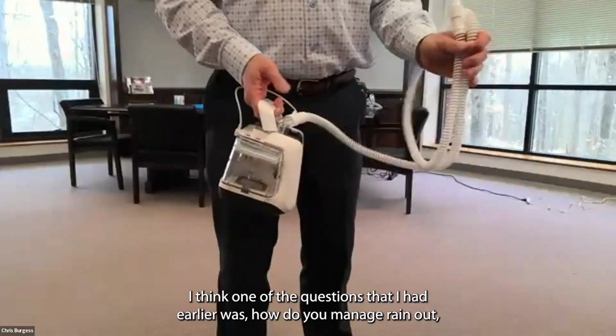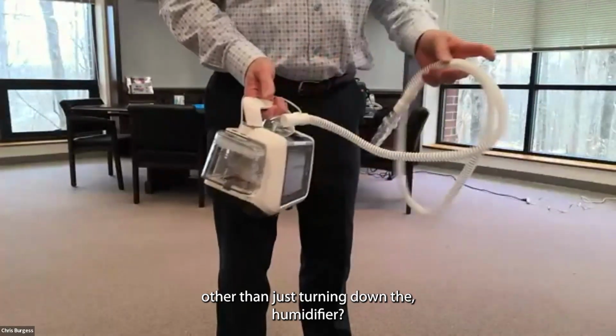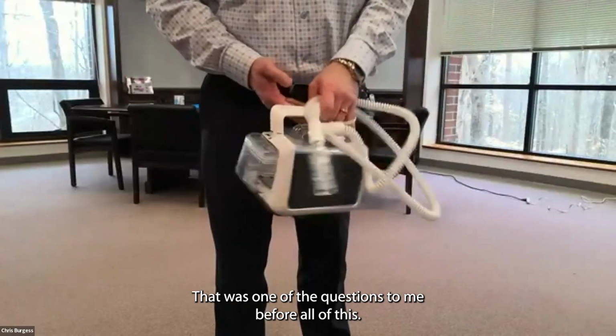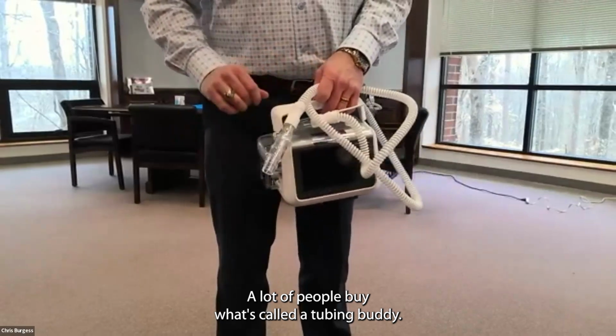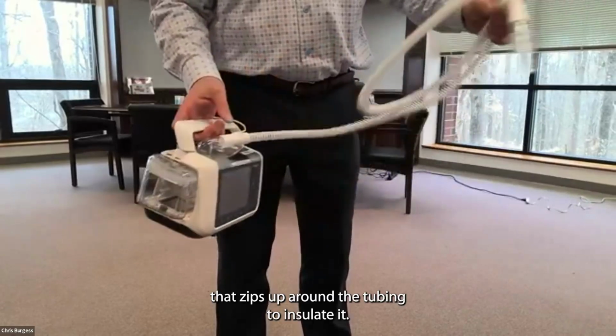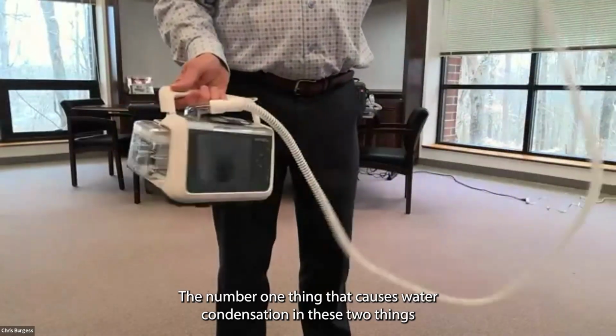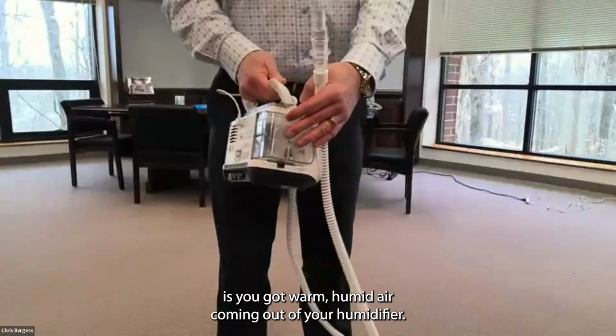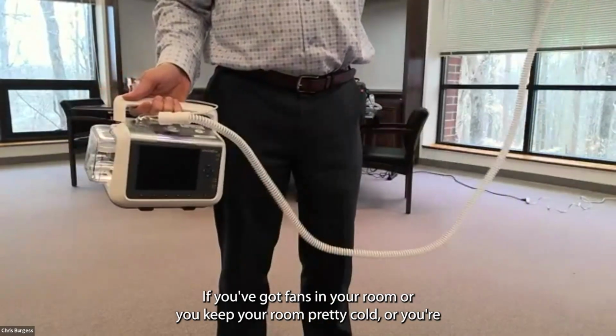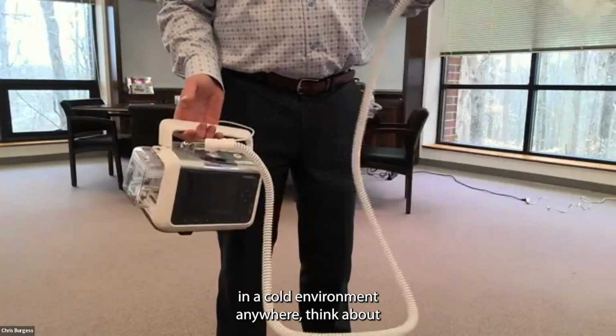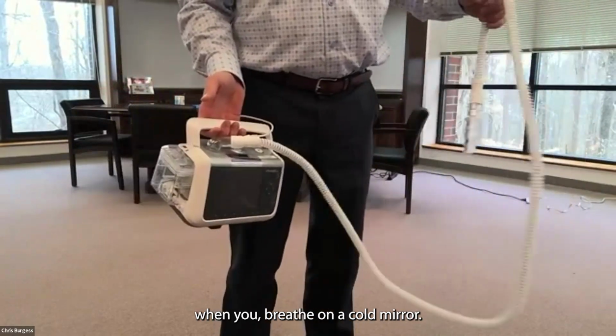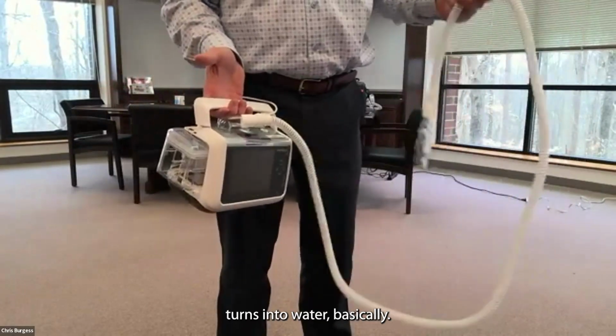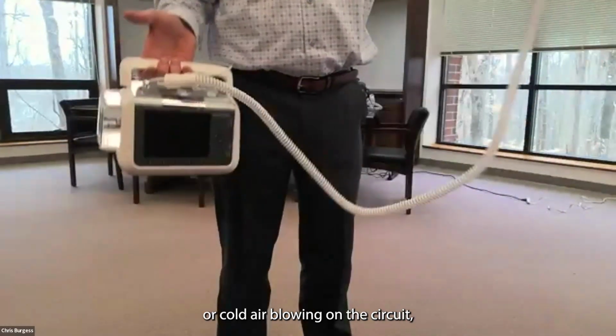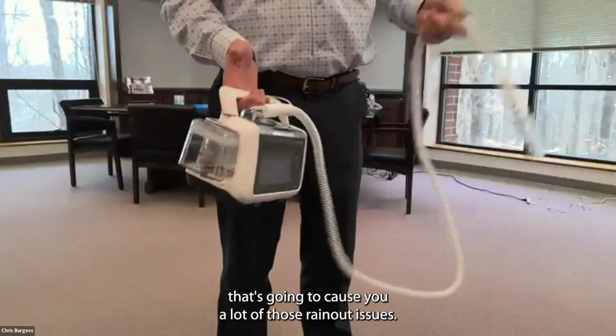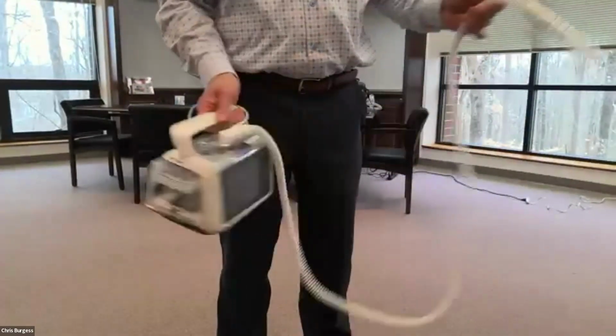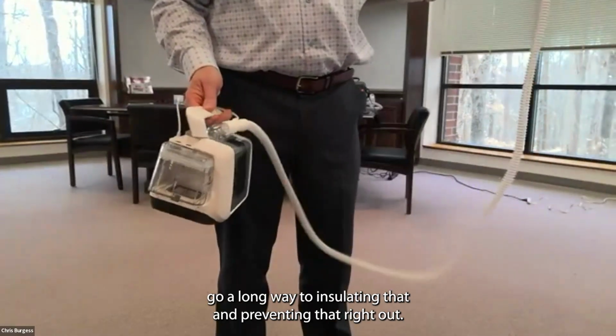I think one of the questions I had earlier was, how do you manage rain out other than just turning down the humidifier? That was one of the questions sent to me before all of this. A lot of people buy what's called a tubing buddy - it's just a tubing wrap, a cloth wrap that zips up around the tubing to insulate it. The number one thing that causes water and condensation in these tubings is you've got warm, humid air coming out of your humidifier. If you've got fans in your room, or you keep your room pretty cold, or you're in a cold environment anywhere - think about when you breathe on a cold mirror, all that condensation turns into water basically. So if you've got warm, humid air going through the system and cold air blowing on the circuit, that's going to cause you a lot of those rain out issues. And that's what having the integrated heated wire tubing prevents. But if you don't have heated wire tubing, those tubing wraps go a long way to insulating that and preventing that rain out.